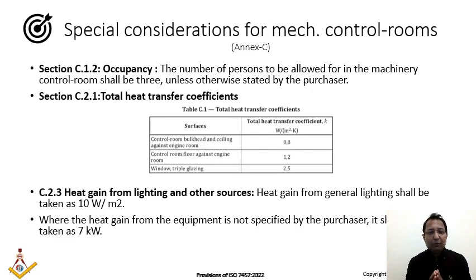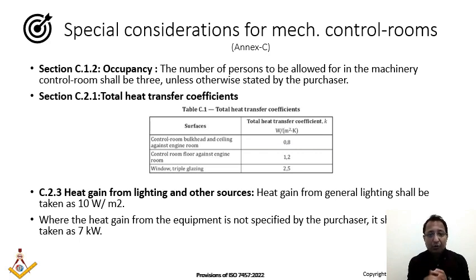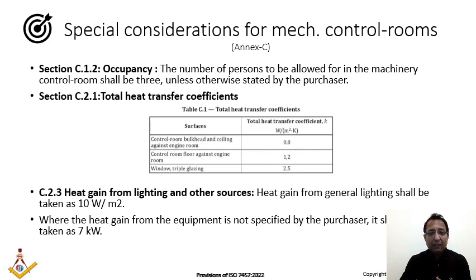Annexure C provides special considerations for machinery control rooms. Section C.1.2 states that the occupancy — number of persons — in the machinery control room should be 3 unless otherwise stated by the purchaser. The specific U-values for the control room are: bulkhead and ceiling against the engine room = 0.8 W/m²K; floor against the engine room = 1.2 W/m²K; windows with triple glazing = 2.5 W/m²K.